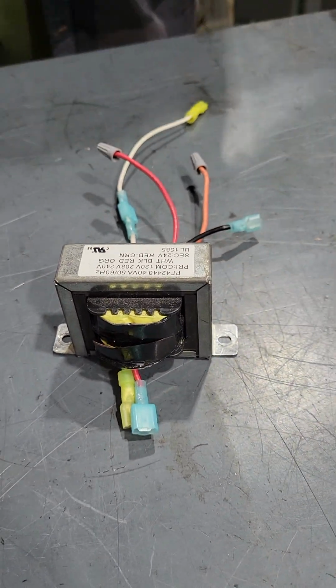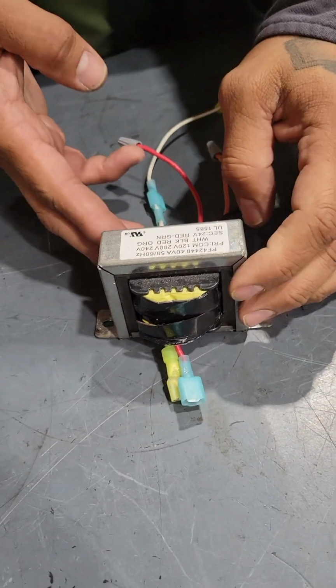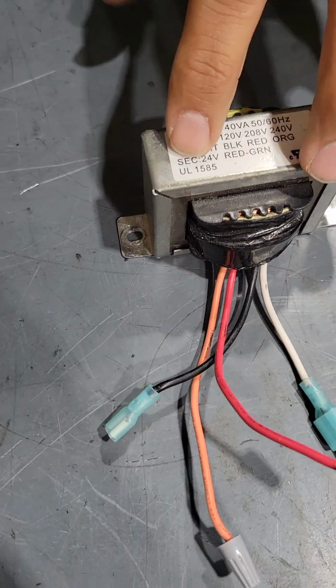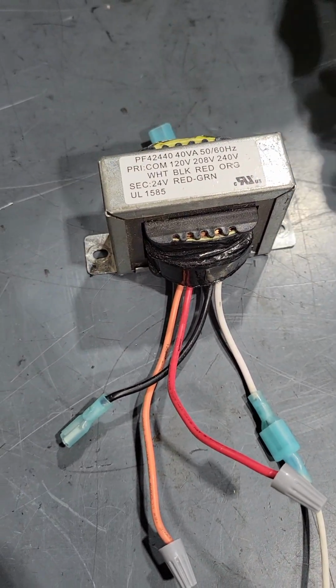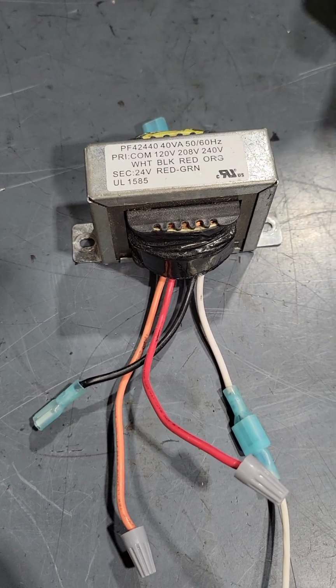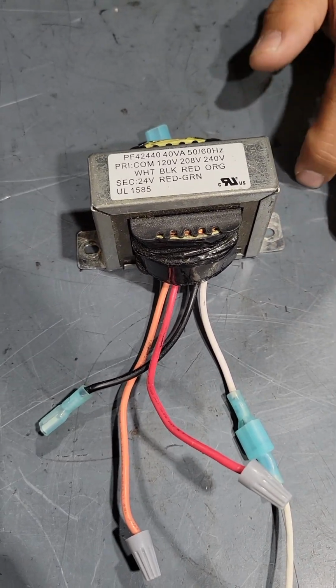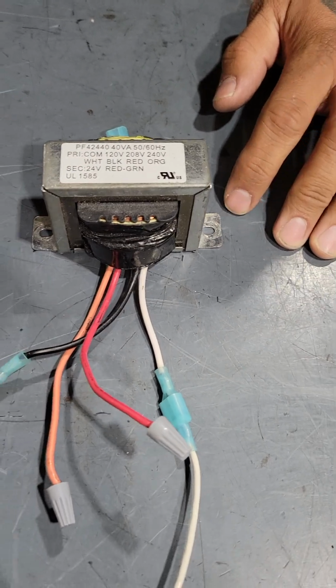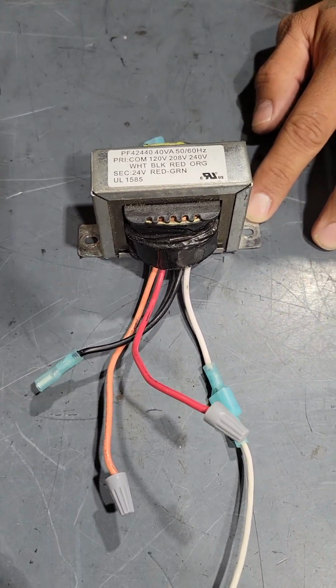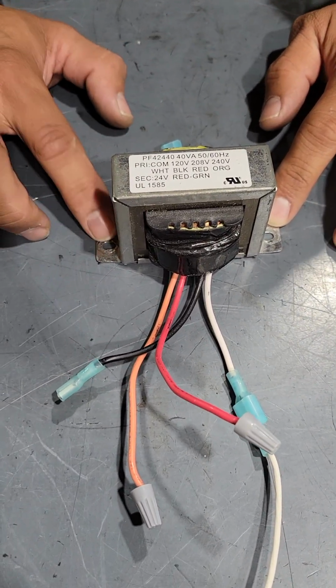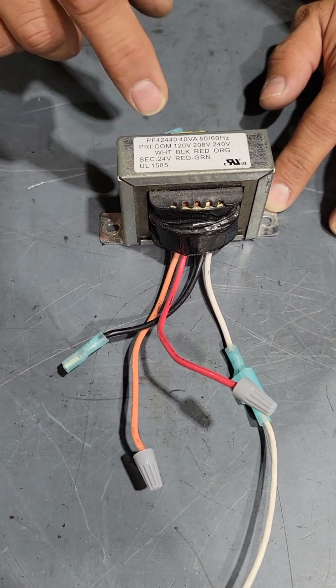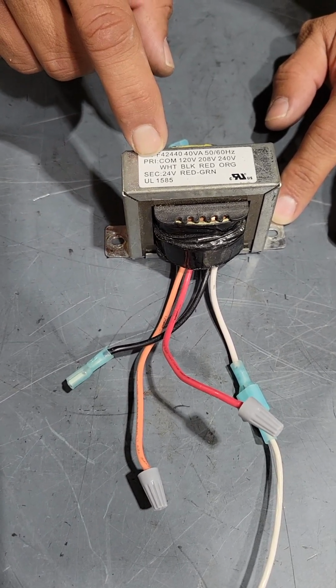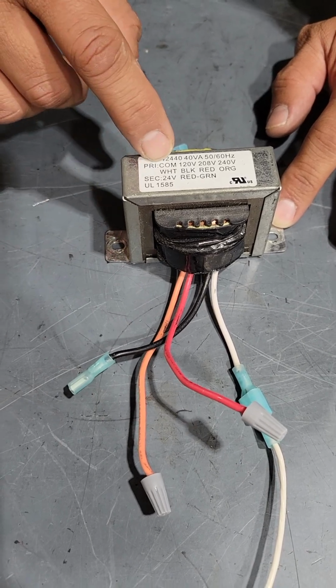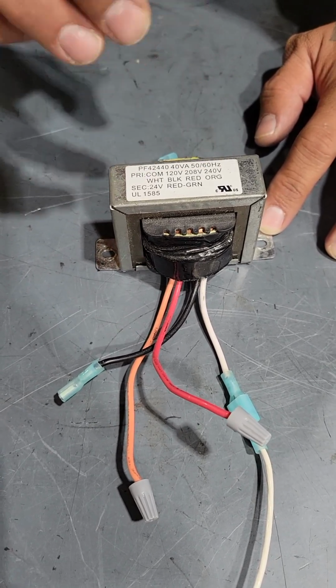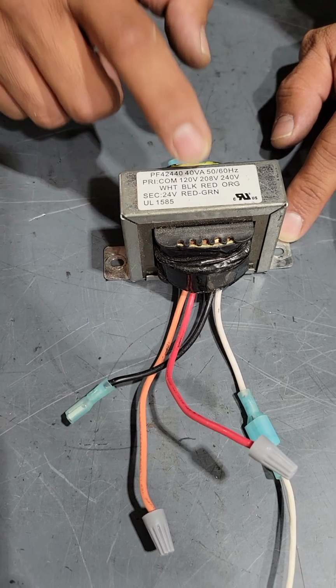The transformer. This is going to be a crucial component inside of the residential package units, split systems, things like that. You'll have transformers of various sizes, but this is the most common in residential. In this case, you read them. The primary side is going to be the side where all your line taps are, and in this specific transformer we have multiple taps. That's why you've got so many wires in.